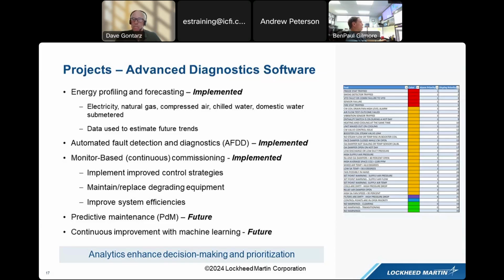Well, we actually started doing this in 2007 when we built those first aircraft paint bays, because the systems were so complicated there was no way a normal day-to-day operator could look at hundreds of points on a graphic and decide, oh, that's the problem right there. So we realized we had to help. We had to come up with some kind of fault detection and be able to tell them what's wrong when there is a problem. We expanded that and applied it to our 700 or so air handlers and units across the site so we'd have fault detection on all of our hardware.